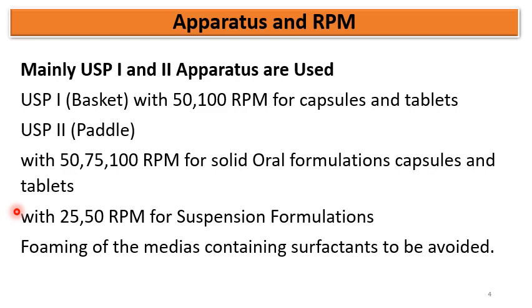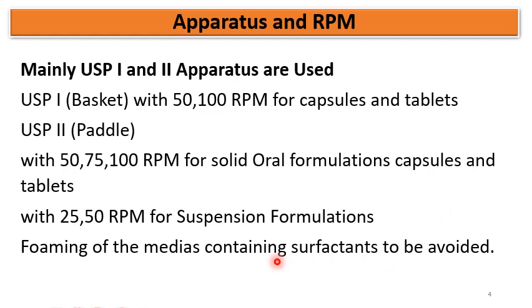For apparatus-2 with oral suspension formulations, 25 and 50 RPM can be selected. Since suspension formulations do not require disintegration, a lower RPM suffices. Also, when using apparatus-2, excessive RPM may cause foaming if the media contains surfactant. Foaming of surfactant-containing media must be avoided — that is a very basic requirement.